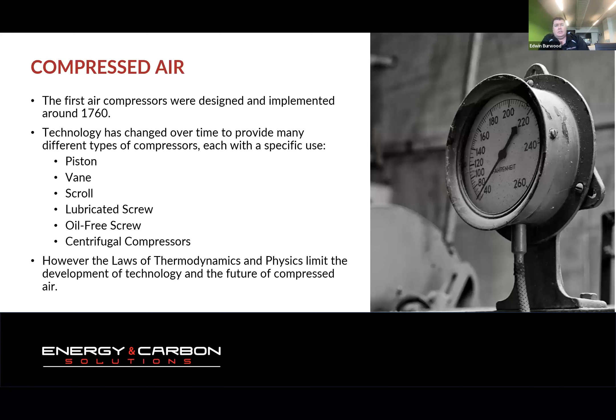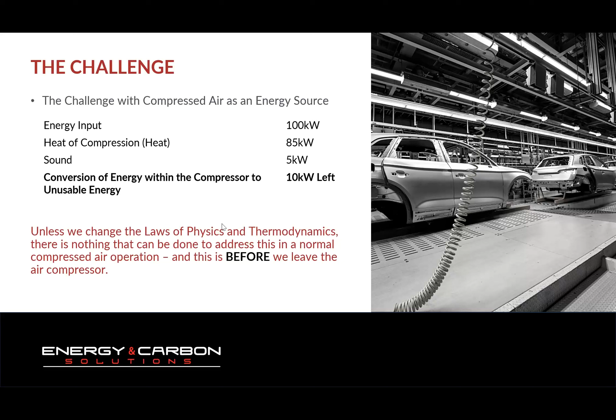So the challenge with compressed air as an energy source: if we have an air compressor whereby we put 100 kilowatts in, we're essentially losing 85 kilowatts through heat of compression, or heat and sound. If I lose 85 kilowatts in heat back to the atmosphere or through a water stream to keep the compressor cool, and about 5 kilowatts through sound, I end up with about 10 kilowatts of usable energy. So before we've even left the compressor, we've lost almost up towards 90% of the input energy into the compressor and the compressed air stream. Unless we can change the law of physics and thermodynamics, there's nothing that can be done to address this in a normal compressed air system, and this loss generally happens before we even leave the air compressor.